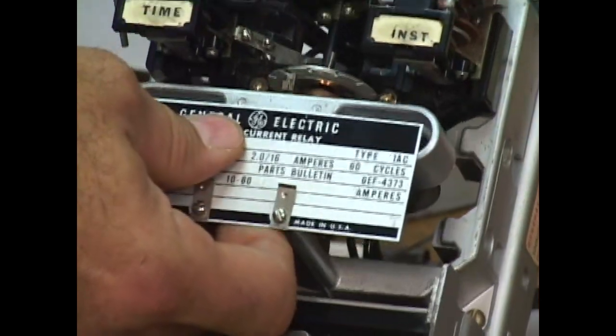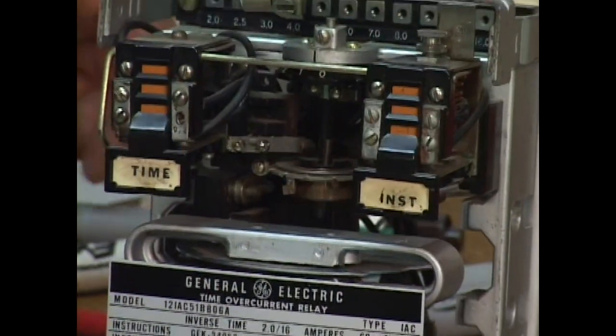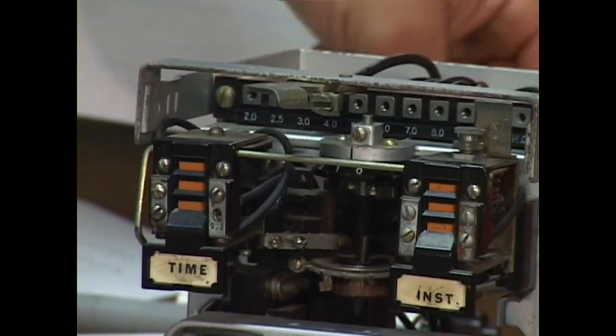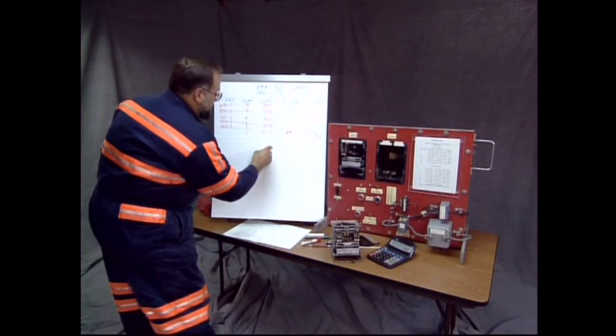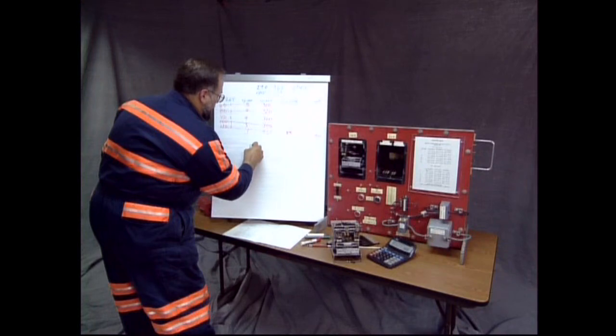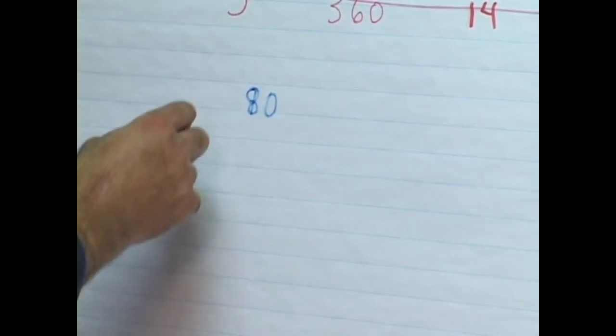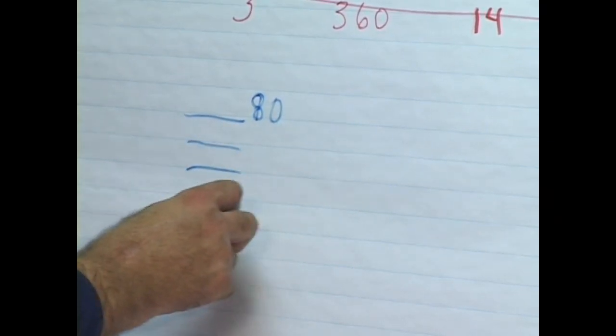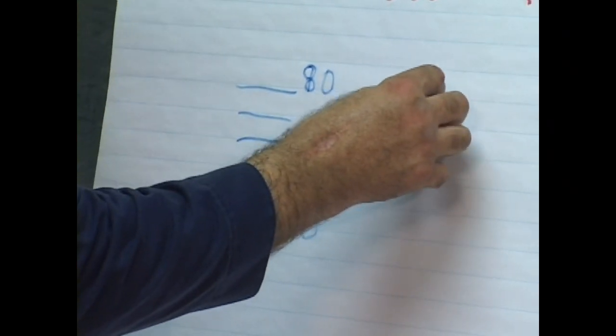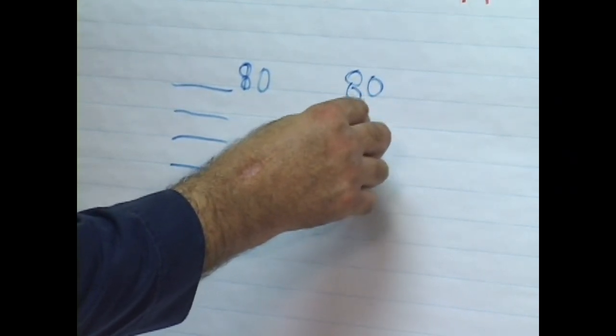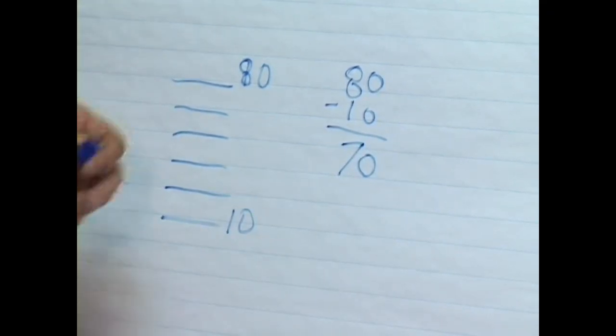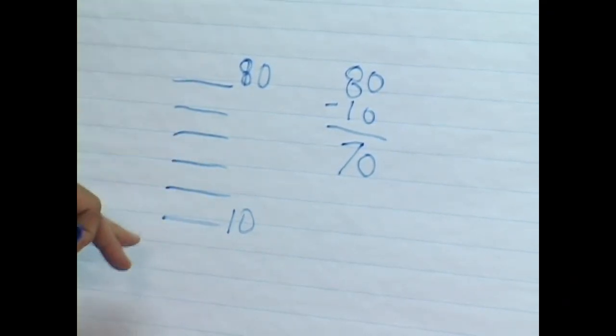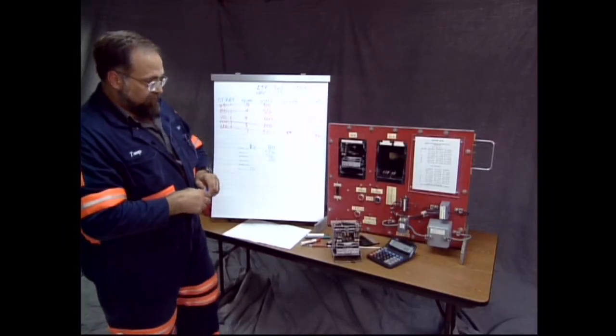This relay has an adjustable core, and the core has a span from 10 to 80. This one here has 10 to 80, 80 being the max and 10 being the minimum. That's the range of this device. Let's say the span of this device, how much adjustment you have, is the difference between 10 and 80. You have a range of 70 amps that this device will adjust into. So 70 amps between the minimum and maximum.